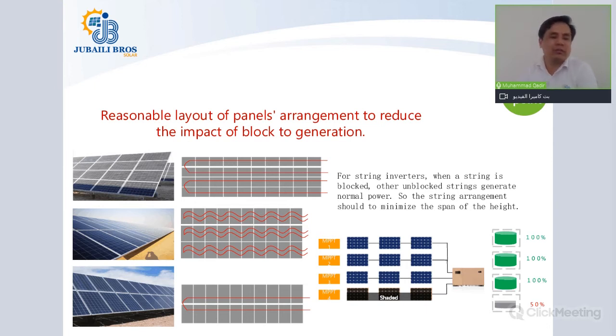If you make a string of all the solar panels which are shaded, and do not mix it with the solar panels at the second, third, or fourth level, you will get the benefit that it will not affect the other solar panels. But if you mix the shaded solar panels with the solar panels in the second, third, and fourth rows, this will definitely affect the output in case of such shading. So what we suggest is that you make your stringing of the lower row solar panels into one string, the second row into a second string, the third row into a third string, and the fourth row into a fourth string. The lower row should be connected to one MPPT, the second row to a different MPPT, the fourth to a different MPPT. Similarly, you will connect them all to different MPPTs.